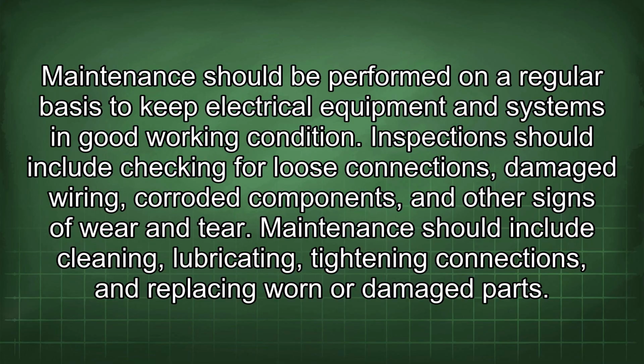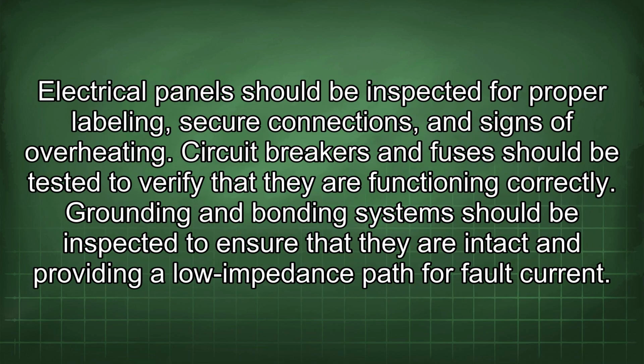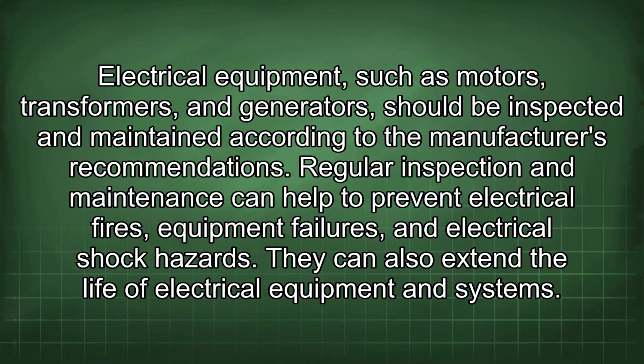Maintenance should include cleaning, lubricating, tightening connections, and replacing worn or damaged parts. Electrical panels should be inspected for proper labeling, secure connections, and signs of overheating. Circuit breakers and fuses should be tested to verify that they are functioning correctly. Grounding and bonding systems should be inspected to ensure that they are intact and providing a low impedance path for fault current. Electrical equipment, such as motors, transformers, and generators, should be inspected and maintained according to the manufacturer's recommendations.